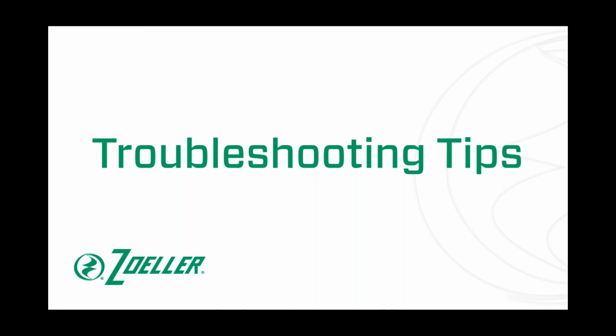Sometimes you're going to need to check it to make sure that you have voltage. Sometimes you're going to need to check it to make sure you don't. If you're having a problem with a panel and you think it might be a voltage issue, maybe you think there might be a problem with a component inside the panel, get out your multimeter or your amp probe, put it on voltage, and check the voltage. Check it as close to the pump as possible. That will help you make sure that it's not a component in the panel. When you're doing this, if you have an amp probe, be sure to check that amp draw too.